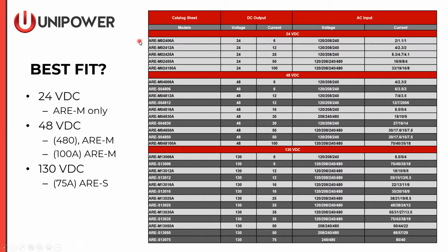So there are times when simply the DC output or AC input is determining which model you're going to use. So for instance, if you have a 24-volt output application, you'll see that your choice is the ARE-M. That comes in 24 volt and various current outputs. There are other times in a 48-volt application where you may need 480 volt in on the AC input or 100 amp out on the DC output. And again, here it's the ARE-M would be your only choice there. And there's also an instance in the 130 volt applications. If you need 75 amp output, then again, at the bottom of the chart here, the only option is the ARE-S. So there again, sometimes it is simply the specifications that determine which model you use. And John Rambo, I'm going to ask, are there applications or engineering design differences that might determine which one of these models that you use?